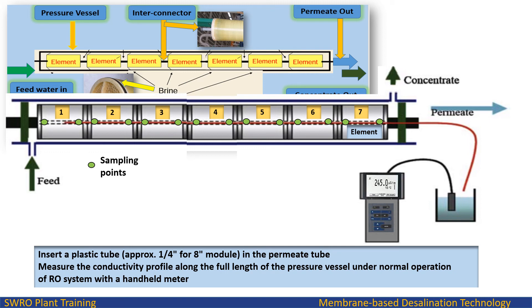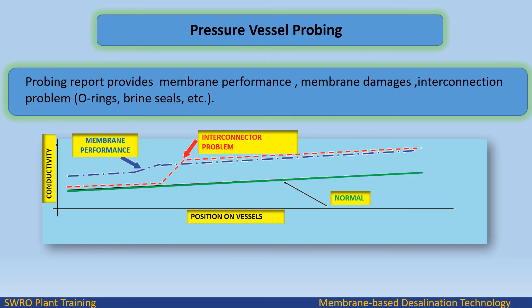Measure the conductivity profile along the full length of the pressure vessel under normal RO system operation using a hand-held meter. Samples are collected for each location as per the sampling point locations defined in the pressure vessel probing procedure.